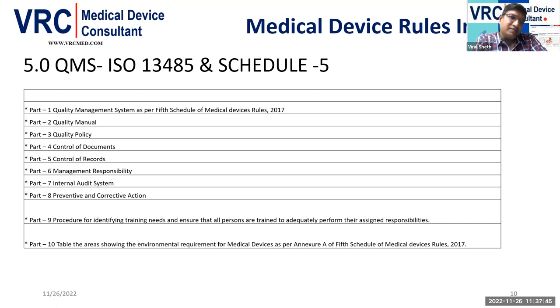Part 10 is somewhat different than the ISO 13485 requirement. That is mentioned in Annexure A of the fifth schedule of the medical device rules. So as a manufacturer, when you are going to manufacture your device, your setup should meet some environmental requirements, as defined in Annexure A.